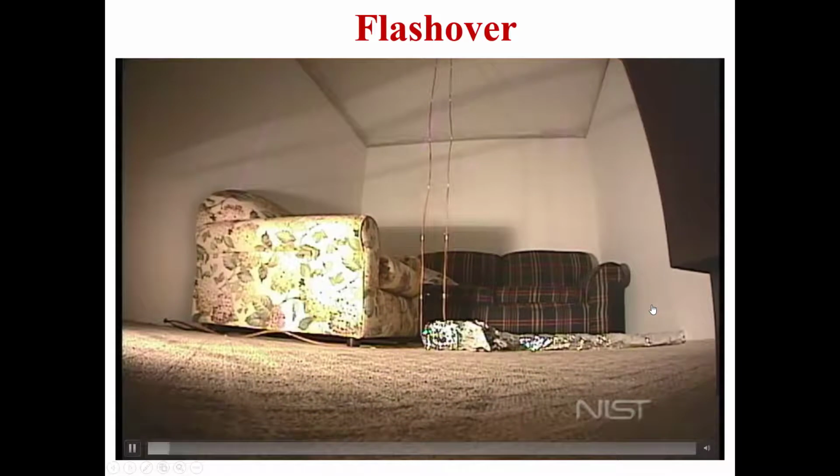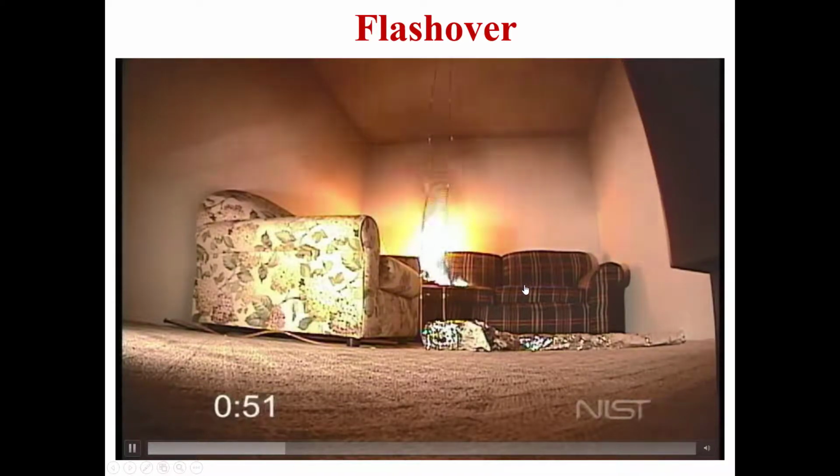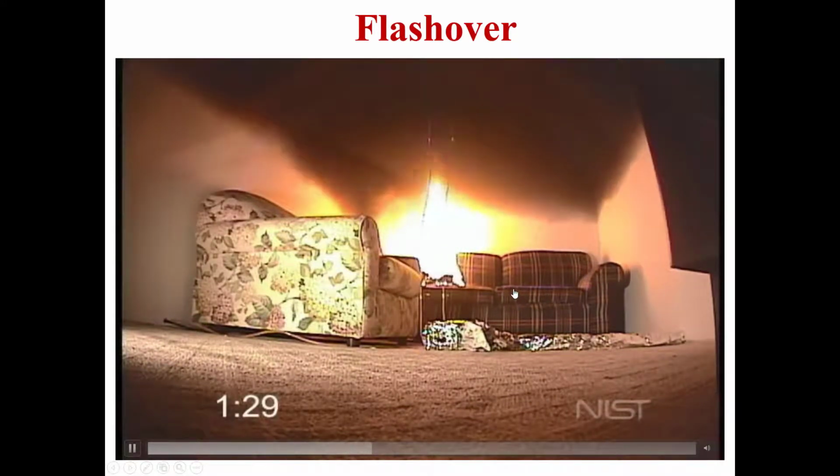Here's another video demonstrating a flashover. So we have the ignition of the fire in the incipient stage, and we'll shortly start to see the development of a plume of smoke and heat. It goes up, hits the ceiling, and then we have the formation of the ceiling jet. One other thing we're going to point out to you here along the couch as the fire grows and goes through the growth stage is we're going to start to see pyrolysis, which is that off-gassing of the solid fuels as they convert into a gas. And then we'll also see it along the floor, but we'll first see it here on the sofa.